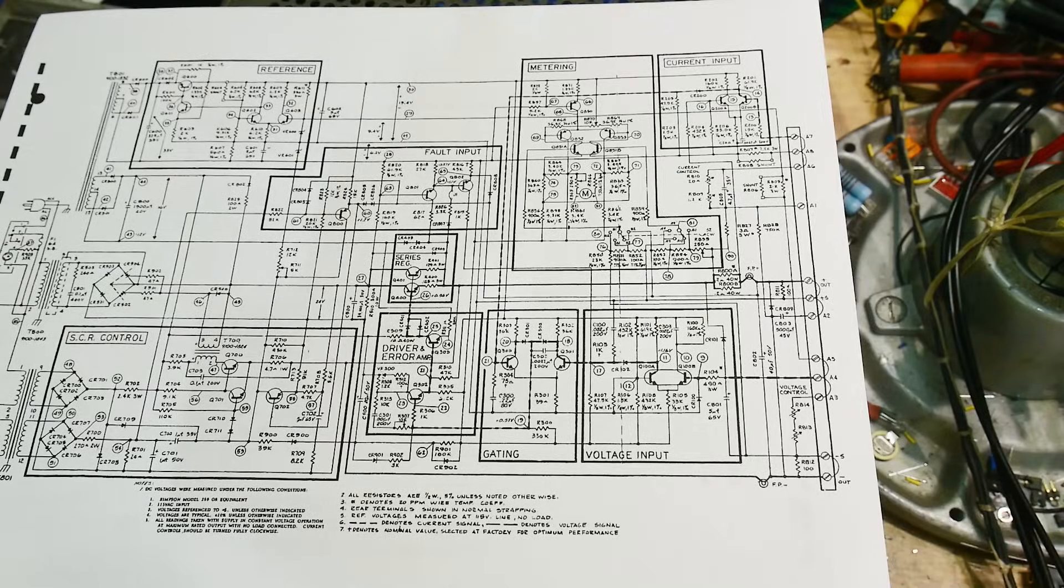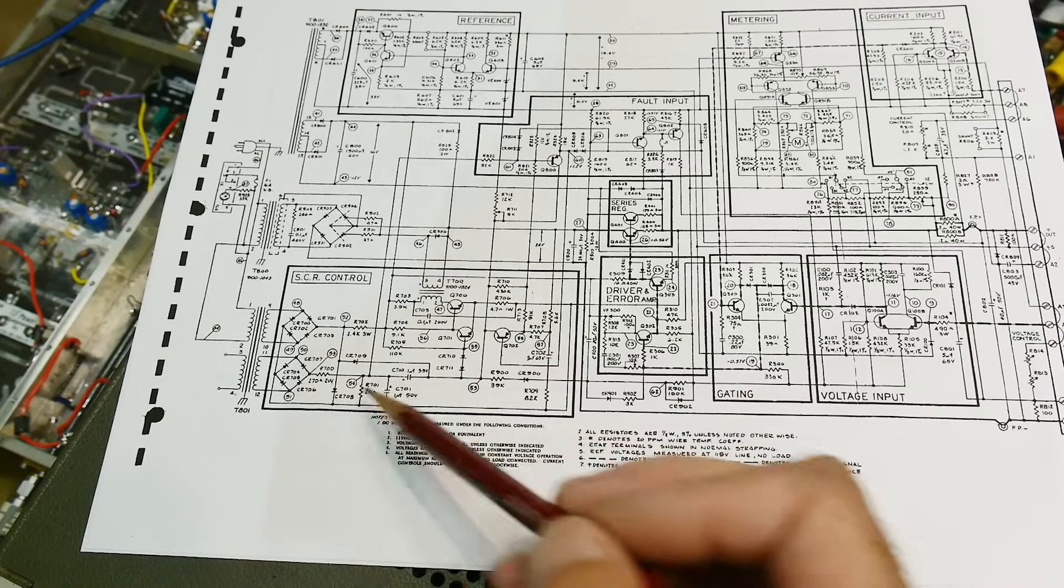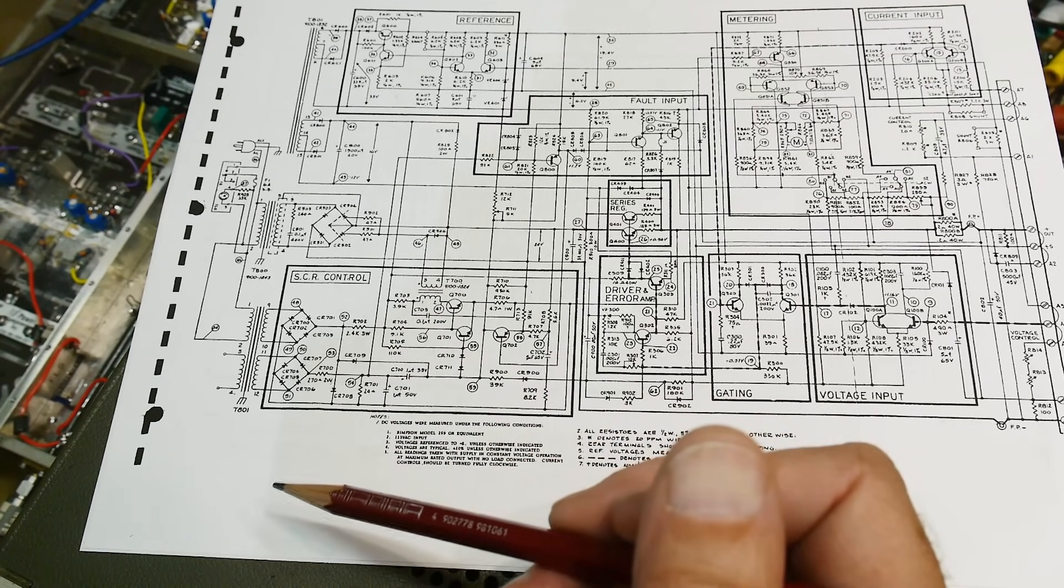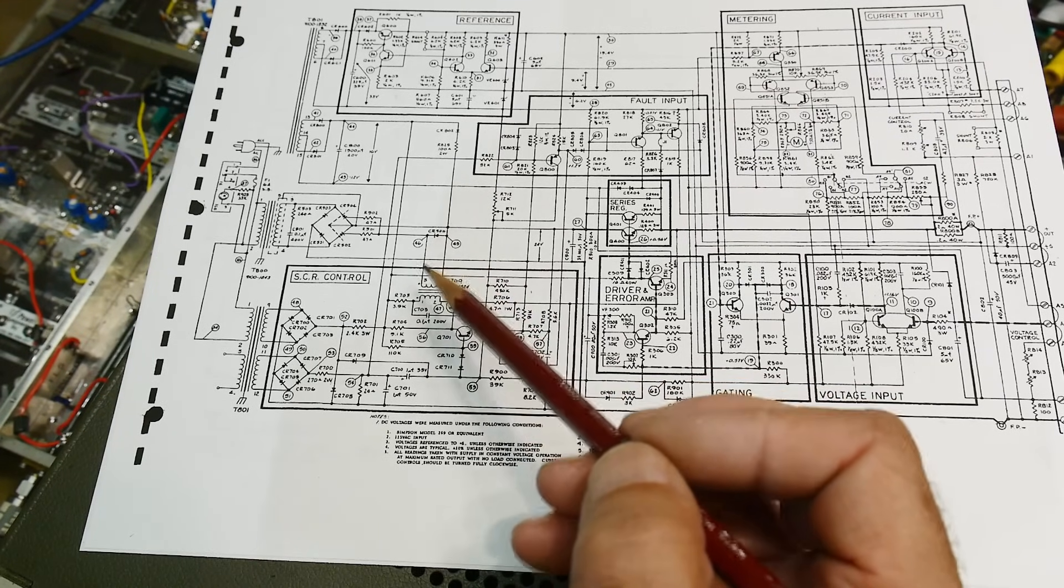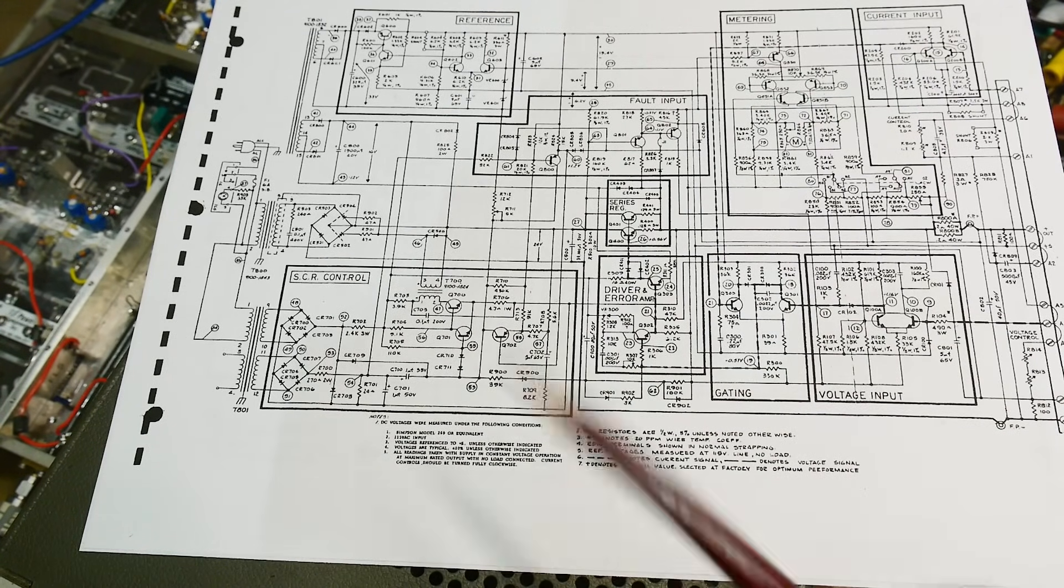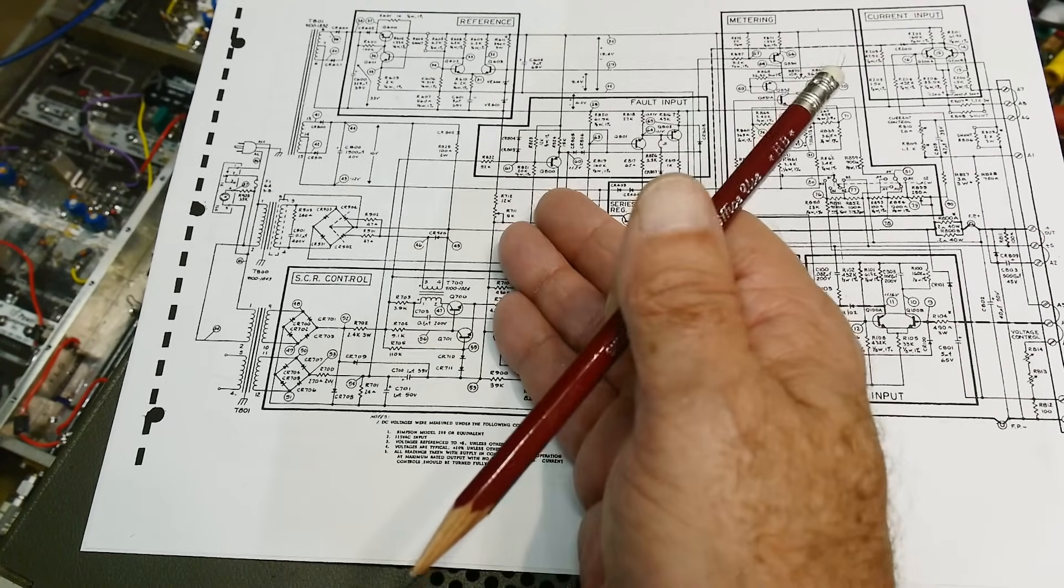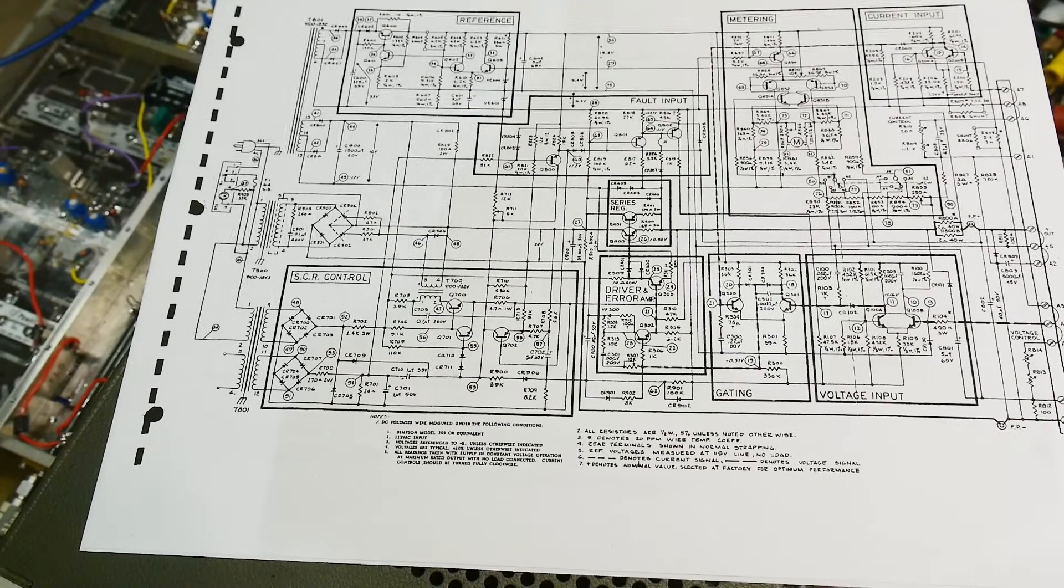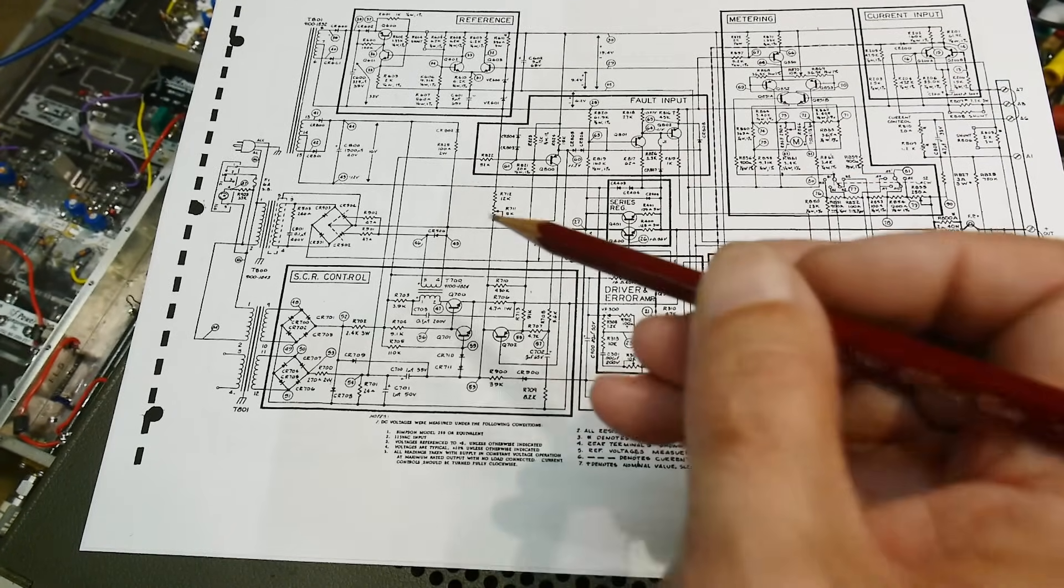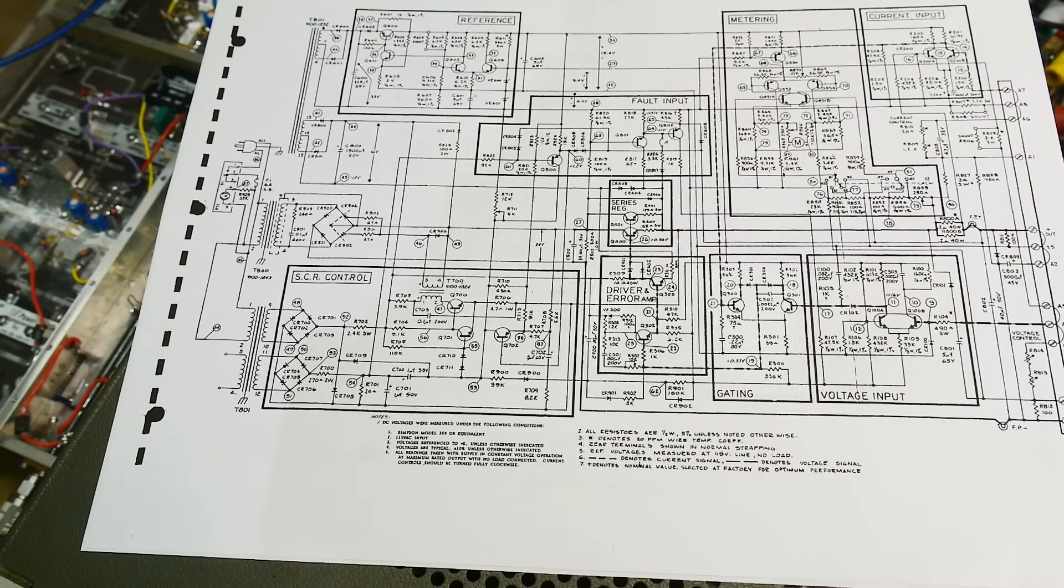But this one has this fancy circuit from Harrison laboratories. Harrison invented this really cool circuit here, which is a pre-regulator and it is very clever. So you don't want to always be dropping all of the voltage all of the time. You would like to have the input match the output. So if you were going to force five volts, you'd have the input at seven volts. If you wanted to force 10 volts, you'd have the input at 12 volts. Some power supplies have several taps on the transformer and then they'll have switching. They'll have relays that switch in the different taps. Well, this one does something even fancier.